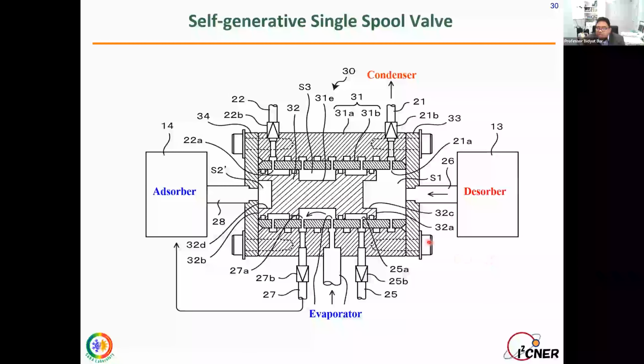A kind of single spool valve. This is the valve here. In the desorption bed, we have the high pressure, so the vapor pushes this spool. This vapor through this channel can reach the condenser, like in the single stage cycle. From the evaporator, our vapor goes through this channel, and through this channel it reaches our adsorber bed. So adsorption is happening in this bed, desorption is happening in this bed, and the desorbed vapor goes to the condenser.